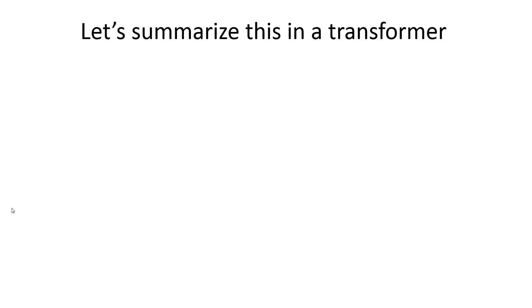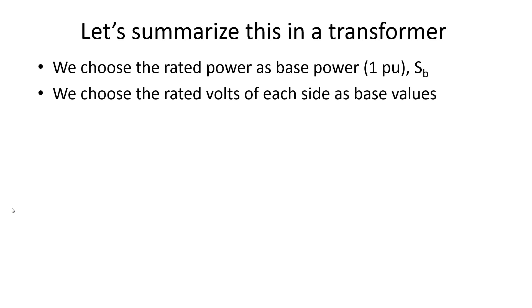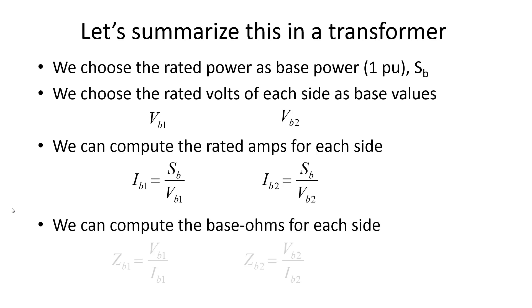Let's summarize for a transformer. We choose the rated power as the base power — that is one per unit. We choose the rated volts of each side as base values for the primary and the secondary. Then we compute the rated amps for each side. For ohms, we divide base volts by base amps, or more frequently, we divide the square of the base volts by the power base.